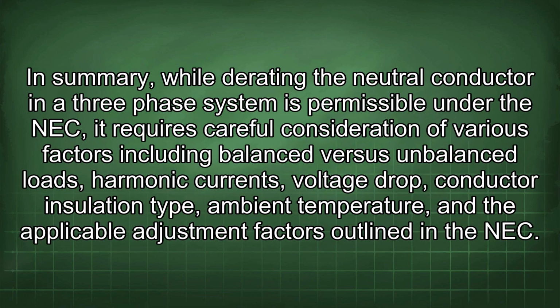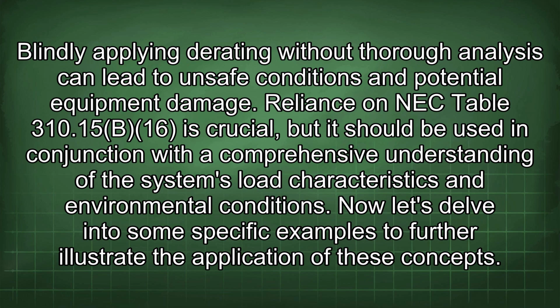In summary, while derating the neutral conductor in a 3-phase system is permissible under the NEC, it requires careful consideration of various factors including balanced versus unbalanced loads, harmonic currents, voltage drop, conductor insulation type, ambient temperature, and the applicable adjustment factors outlined in the NEC. Blindly applying derating without thorough analysis can lead to unsafe conditions and potential equipment damage. Reliance on NEC Table 310.15(B)(16) is crucial, but it should be used in conjunction with a comprehensive understanding of the system's load characteristics and environmental conditions. Now let's delve into some specific examples to further illustrate the application of these concepts.